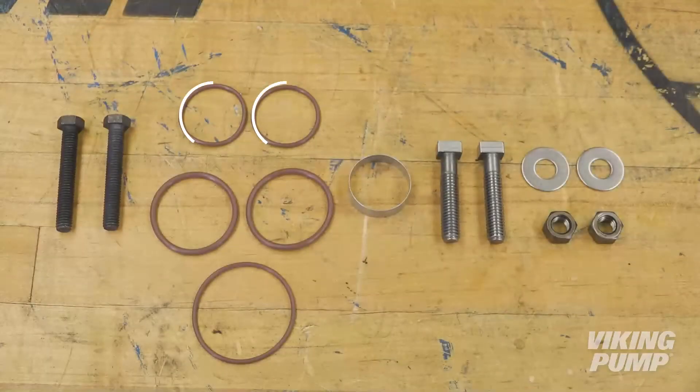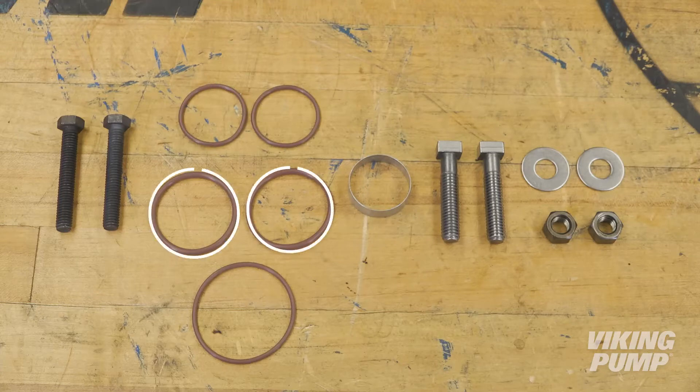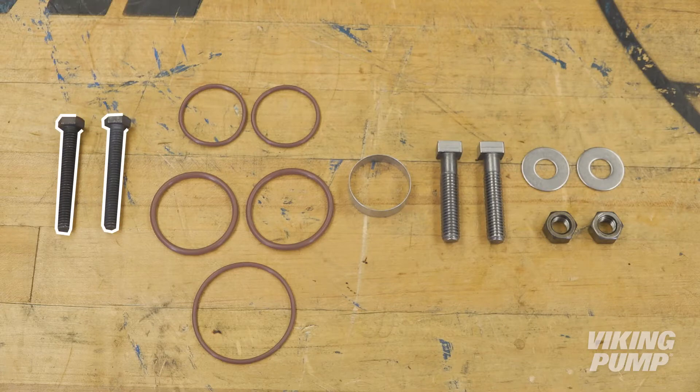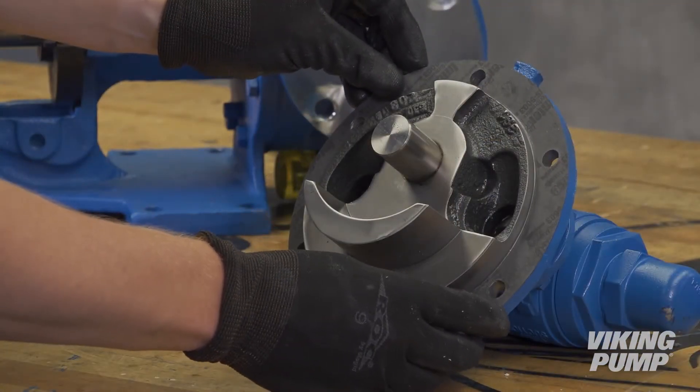The O-ring replacement kit includes the two inner static sleeve O-rings, the two inner dynamic gland O-rings, an outer static gland O-ring, a seal installation sleeve, gland nuts, washers, bolts, two jack bolts for removing the O-Pro Guard seal, and a head gasket in case the head and rotor shaft must be removed.